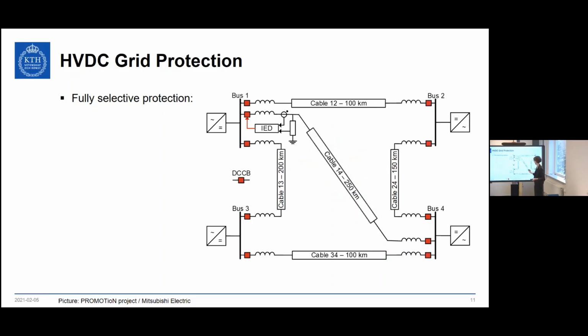But if you have a cable with a remote fault here, it takes a millisecond for the traveling wave to arrive. With a double-ended setup, the IED here detects this close fault almost immediately and starts sending the communication in the same direction. Since optic fiber is also around 200 kilometers per millisecond, you only get a delta t of roughly 0.5 milliseconds. So double-ended is beneficial for remote faults seen from this end, and single-ended is beneficial for close faults.